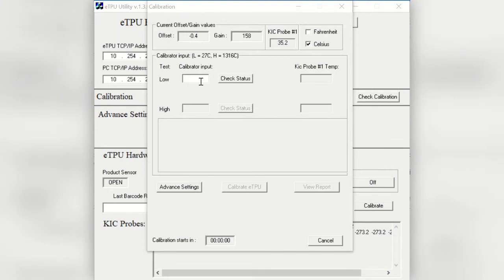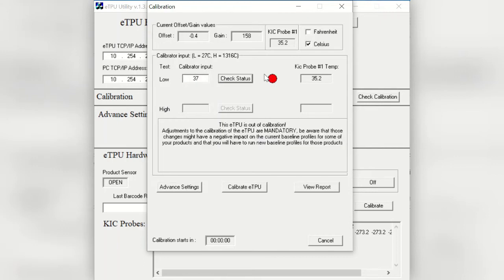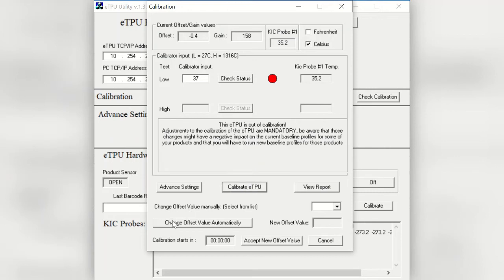Let's see an example of an eTPU that is not within the tolerance. Once again, we set our calibrator to the lower input. We write the same value as in the calibrator into the utility, and we check the status of the calibration. As you can see, it's red. It means that the eTPU is out of calibration and you cannot move to the next step on calibrating to the higher input. Therefore, we should follow the instructions and click on Calibrate eTPU. Next, we click on Change Offset Value Automatically, and we accept new offset values. The change was successful. Now we can see what the change in the offset value does to our readings and that it puts us back in spec.